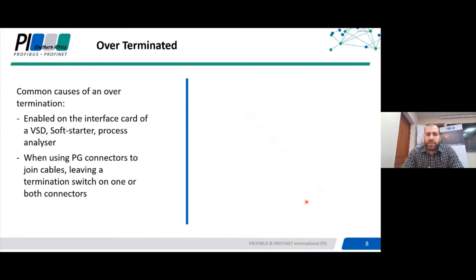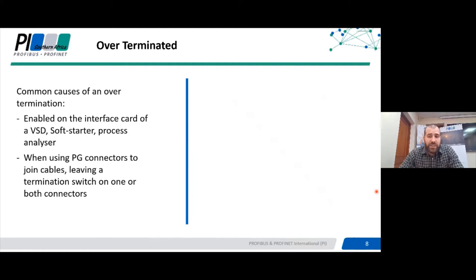Just as bad as an under-termination, if not actually worse, is something called an over-termination. Each segment should have two terminations per segment. If there are more than two terminations enabled or the terminations are enabled at the wrong point, the system would be subject to what I refer to as the segment being over-terminated. From experience, a common place where over-termination is unintentionally enabled is within VSDs, soft starters, and some process analyzers.